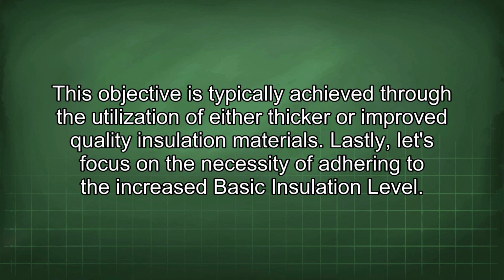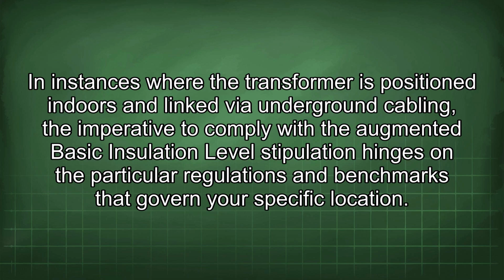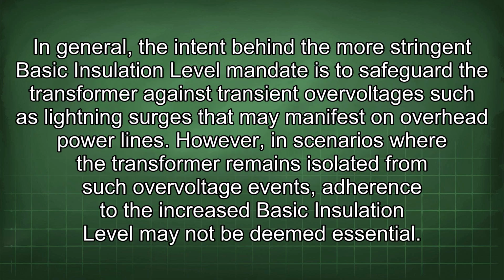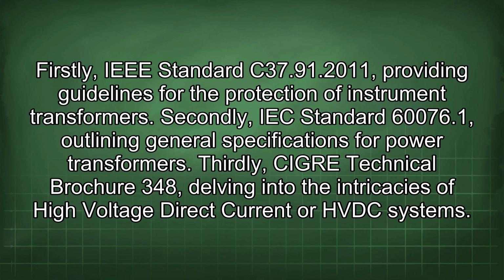Lastly, let's focus on the necessity of adhering to the increased basic insulation level. In instances where the transformer is positioned indoors and linked via underground cabling, the imperative to comply with the augmented basic insulation level stipulation hinges on the particular regulations and benchmarks that govern your specific location. In general, the intent behind the more stringent basic insulation level mandate is to safeguard the transformer against transient overvoltages such as lightning surges that may manifest on overhead power lines. However, in scenarios where the transformer remains isolated from such overvoltage events, adherence to the increased basic insulation level may not be deemed essential.